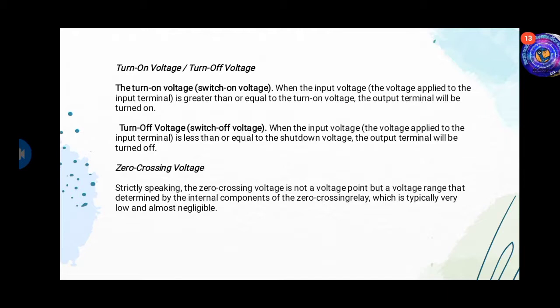Turn on voltage or turn off voltage. When the input voltage applied to the input terminal is greater than or equal to the turn on voltage, the output terminal will be turned on. When the input voltage applied to the input terminal is less than or equal to the shutdown voltage, the output terminal will be turned off. Zero crossing voltage: strictly speaking, the zero crossing voltage is not a voltage point but a voltage range that is determined by the internal components of the zero-crossing relay.